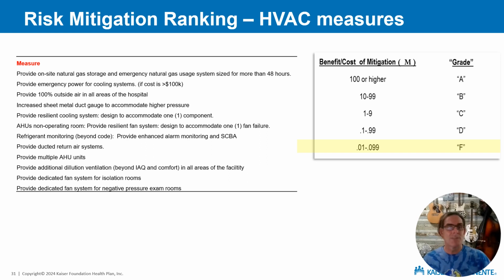And the fact that we have dedicated fan systems for isolation rooms, that's also a code requirement. Dedicated fan systems for negative pressure exam rooms, by the way, is not a code requirement, so we wouldn't do that unless it's a code requirement.